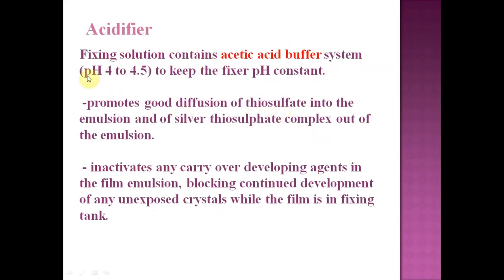The acidifier is acetic acid with an acid buffer system maintaining a pH range of 4 to 4.5, which keeps the fixer pH constant, promotes good diffusion of thiosulfate into the emulsion and of silver thiosulfate complex out of the emulsion, and also inactivates any carryover developing agent in the film emulsion, blocking continued development of unexposed areas while the film is in the fixing tank.